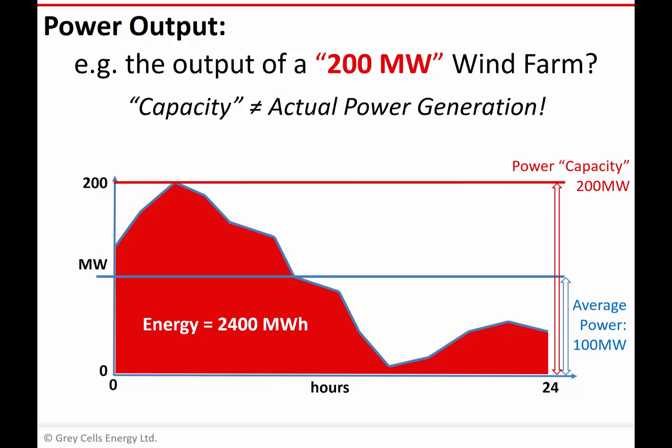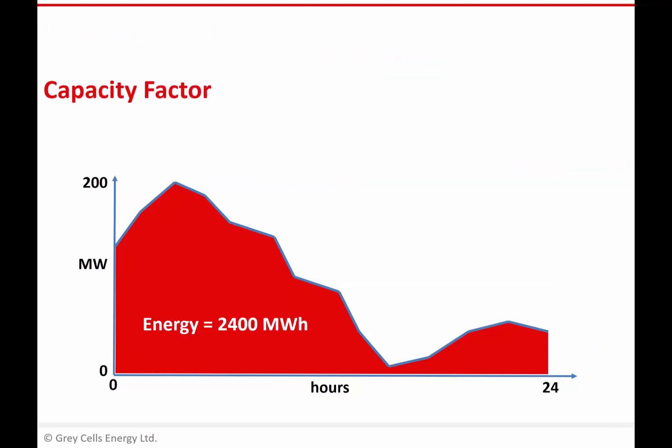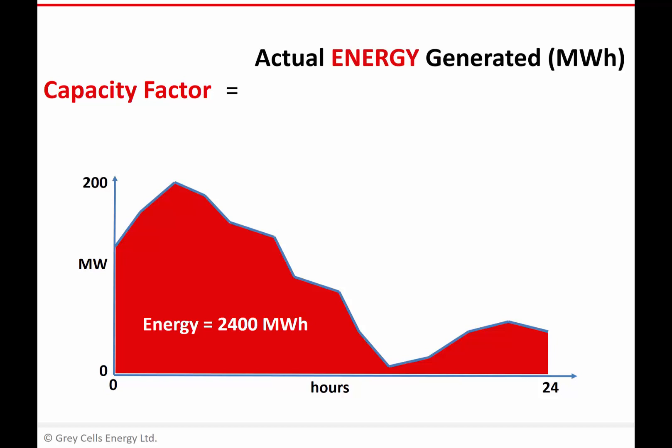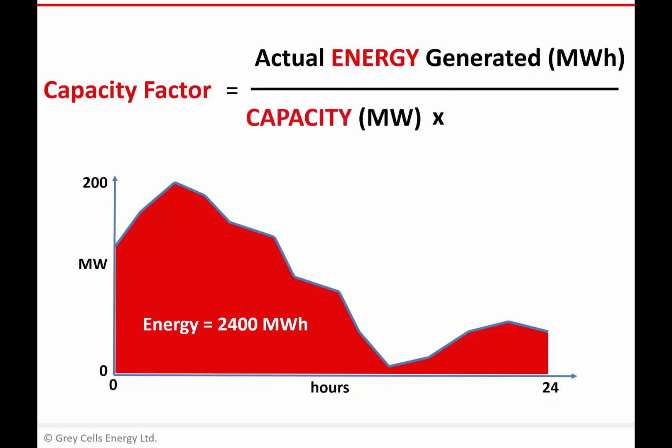This brings us to capacity factor. The power output we're talking about here is the maximum potential power output of the power plant. We can define capacity factor as the actual energy generated over a period of time divided by the capacity of the power plant multiplied by that time period. You can see it's megawatt hours divided by megawatt hours, so capacity factor has no units — it's a dimensionless ratio, most often expressed as a percentage. Importantly, like energy, you can't talk about capacity factor without stating the time period over which you're calculating it.